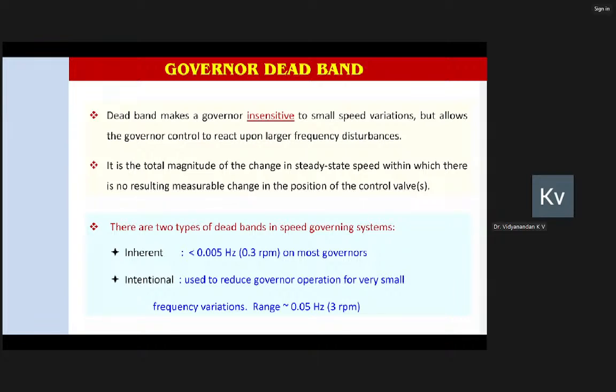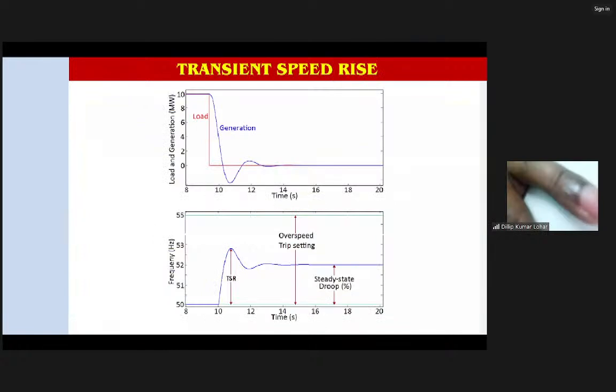That is around 0.3 RPM. That means unless the speed variation is 0.3 RPM or more, the governor will not respond. And the next one is the transient speed rise.